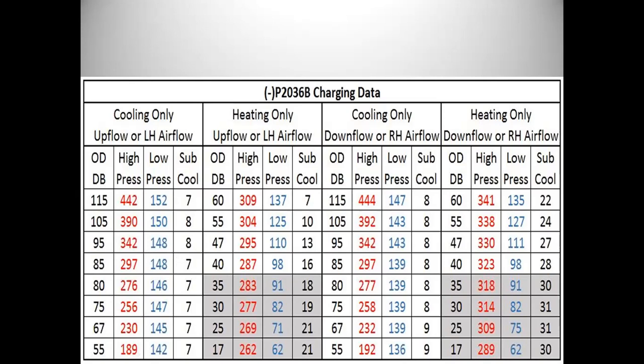Because with inverters, it's better to be a little bit low and let the inverter handle itself with the RPMs, than be over and cause irreparable compressor damage, as well as inverter faults and callbacks, because that's what really kills you. So that kind of sums up the charging for the Rheem inverters.